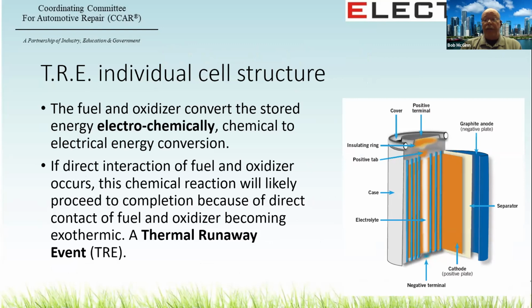So under normal circumstances, the fuel and the oxidizer convert energy electrochemically, chemical to electric energy conversion. If the materials are allowed to react chemically in an electrochemical cell, the fuel and oxidizer convert the chemical energy directly into heat and gas. And because we have a fuel and an oxidizer in a sealed container, we don't need any oxygen. Once started, this chemical reaction will likely proceed to its completion, meaning it will burn completely through as it becomes exothermic. Once a thermal runaway event has begun, the ability to stop it quickly is extremely difficult.